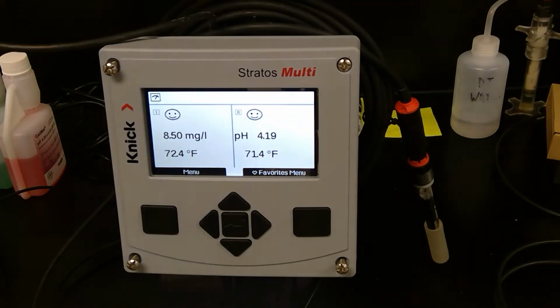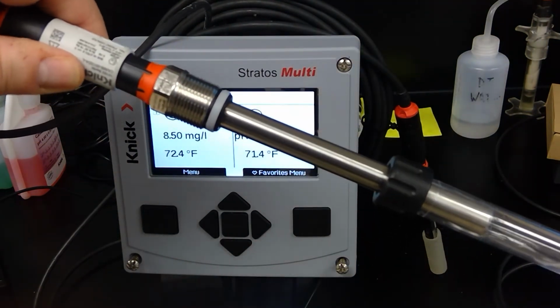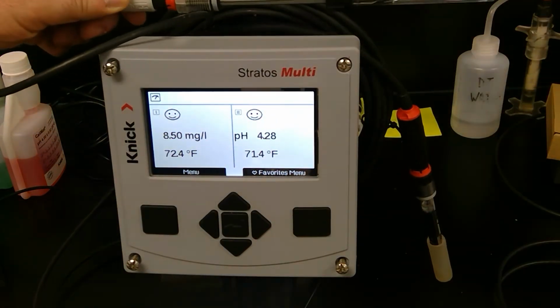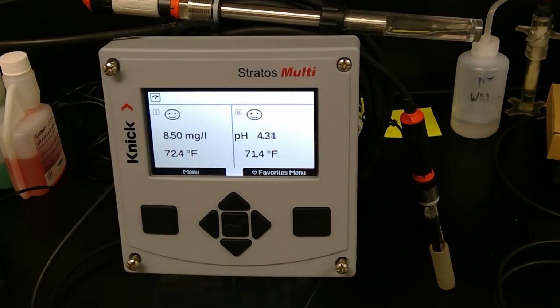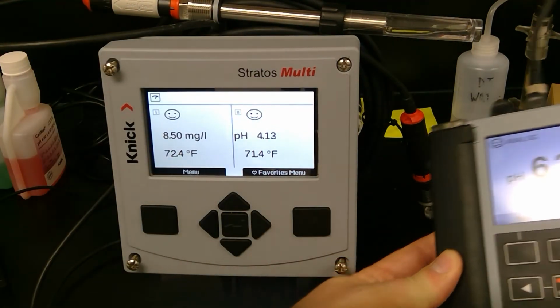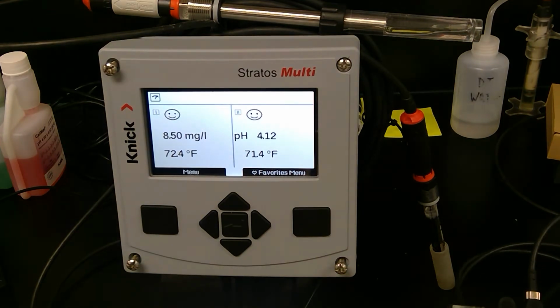The other thing to keep in mind when you go to do a calibration of an amperometric Clark-cell design is that the sensor has to be polarized. What that basically means is that you want to have it connected to a power source, like a transmitter in the shop, or also a Portavo. What we recommend is that if you're going to do calibrations, connect the sensor the night before to either your bench-mounted transmitter or your Portavo. Let it remain powered overnight so the next morning when you come in, it is fully polarized and you won't see any sensor drift or measurement drift once you do your calibration and take it to the field to be put into the measurement application. So let's go ahead and get into the calibration.